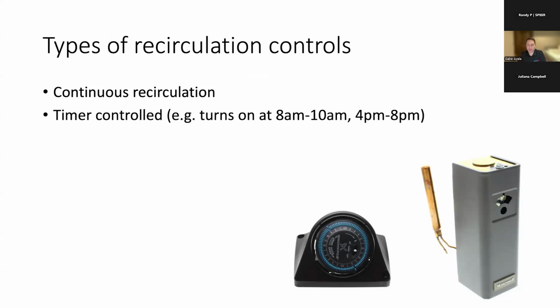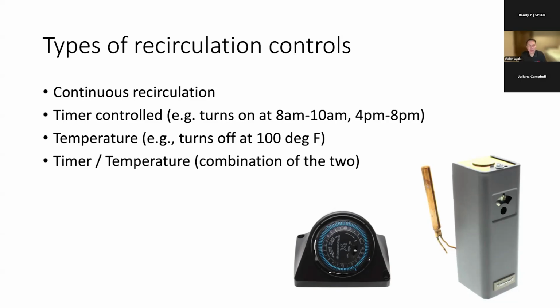And then there are timers, and this is the most often used type of control for a recirculation system. You put a schedule on the pump. Let's have it run from 8 a.m. to 10 a.m. or 4 p.m. to 8 p.m., whatever you want to set it for. You have temperature controls that turn the pump off when the end of the line gets to a certain temperature. And then you have a combination of these two. And I'd say that's probably the most frequent type of control.